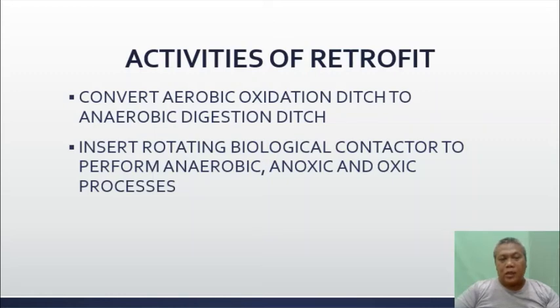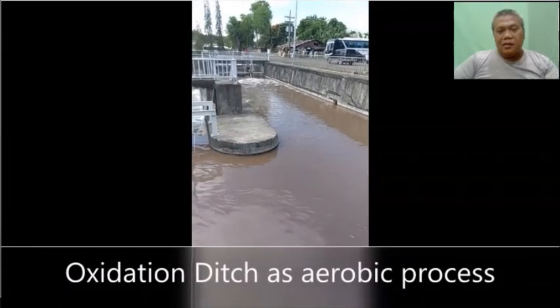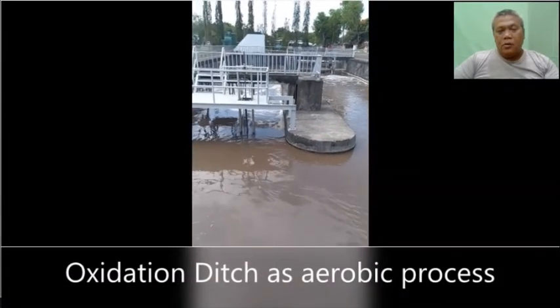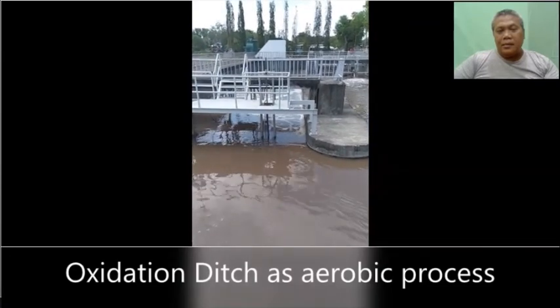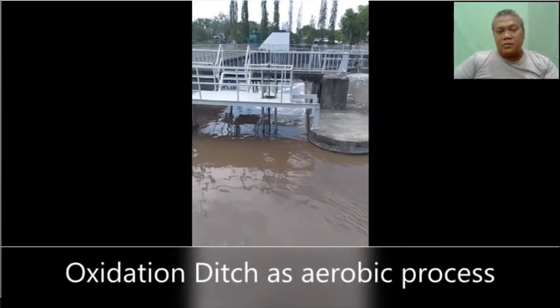Number one, we convert the aerobic oxidation ditch to become an anaerobic digestion ditch. So we take out the aeration part while maintaining the mixing part. Then we insert a rotating biological contactor to perform anaerobic, anoxic, and oxic processes within the system. This is the oxidation ditch while it is still in aerobic process.